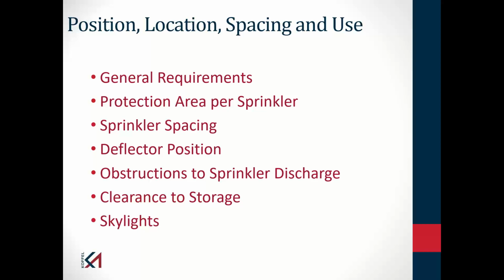And I'll ask the facility, is this wall relatively new? And they tell me, yeah, we installed this wall, but they did not move the sprinklers so that they could meet the sprinkler spacing requirements. While the sprinkler close to the wall might be far enough away, because we do allow sprinklers to be within 4 inches, at least minimum distance from the wall is 4 inches, let me say it that way. But on the other side, the sprinkler's too far from the wall. Logically, the sprinkler is going to discharge water in a circular pattern. So these spacing requirements are really just to try to ensure that we are wetting most of the area of the space. Under obstructions, I'll make a comment as to why I use the word most in that last sentence.